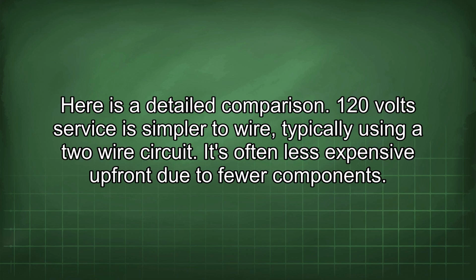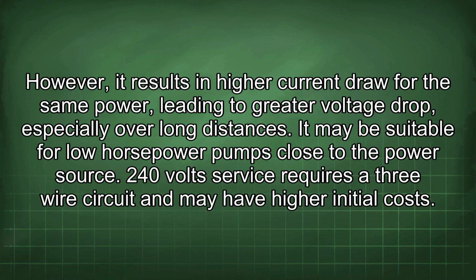120 volt service is simpler to wire, typically using a 2-wire circuit. It's often less expensive upfront due to fewer components. However, it results in higher current draw for the same power, leading to greater voltage drop, especially over long distances. It may be suitable for low horsepower pumps close to the power source.